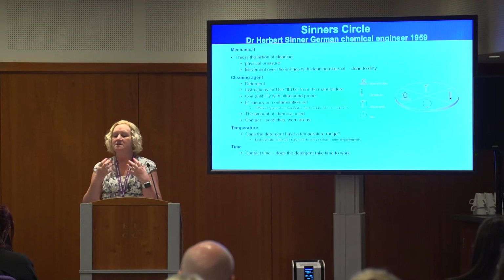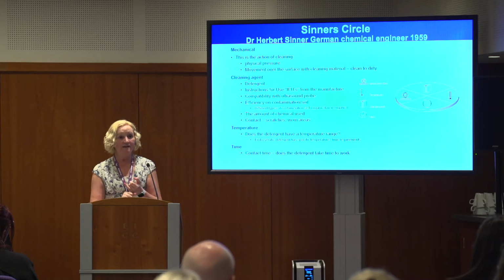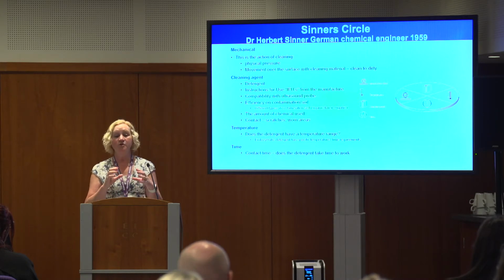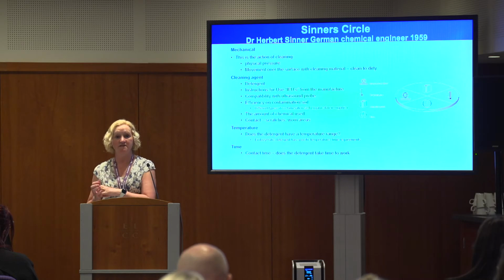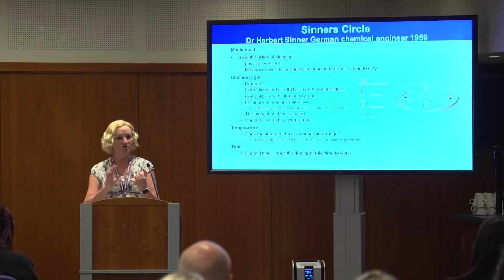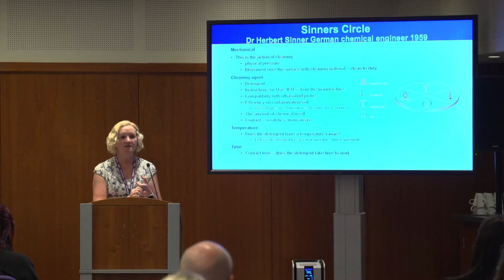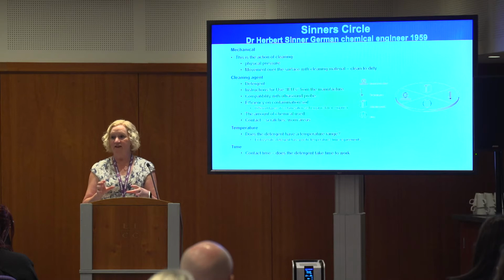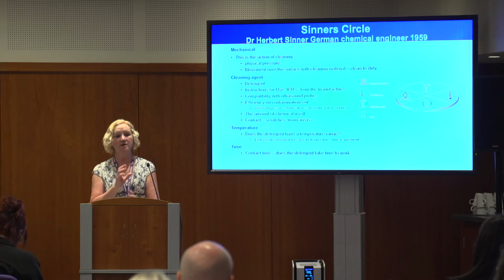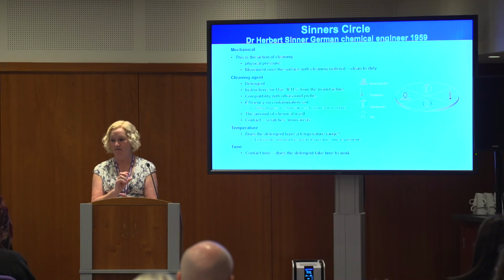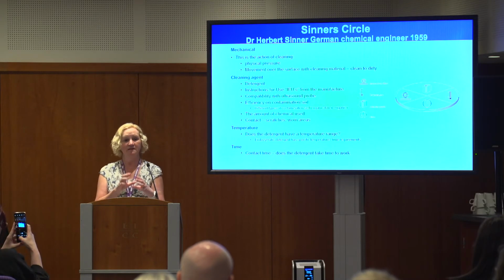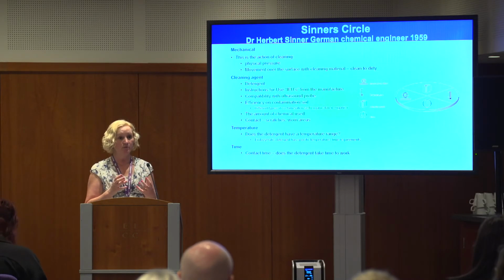When you're talking about cleaning a probe, there are two processes here. There's cleaning and there's disinfection. If you don't have it clean, you cannot disinfect it. If it's got gel on it, if it's got bodily fluids on it, if it's got tea splashes on it, you cannot disinfect it. Whatever's covering that probe will affect the disinfection of it, and the area under that bit of contamination will not be clean. So when you're thinking about the cleaning, it's probably one of the most important parts.